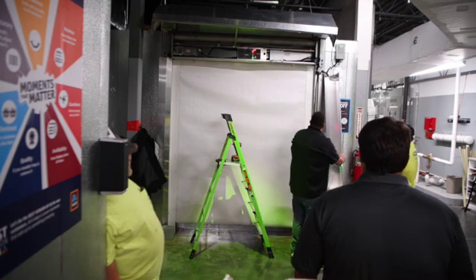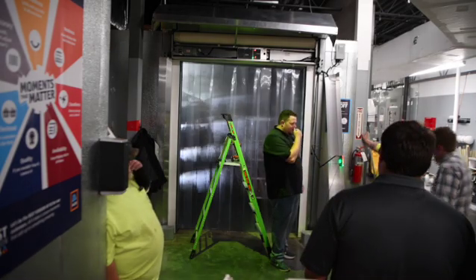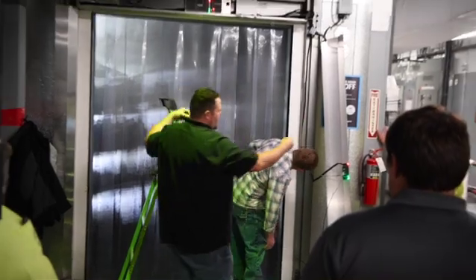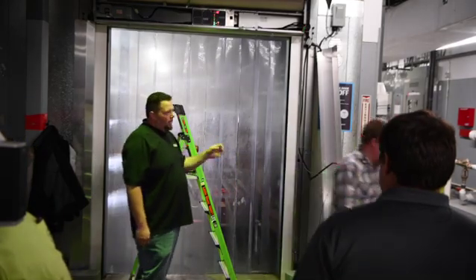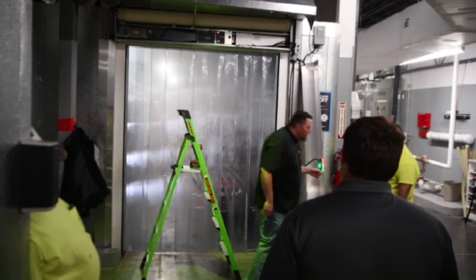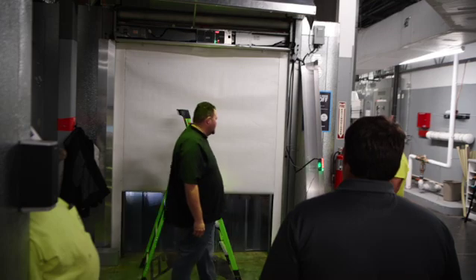You can see on the back side of this, that's the circuit board. That's where we're going to ask you if you're looking for moisture. On the install, which you guys have done plenty of now, these photo sensors, if you don't plug them in on that side, it's all going to come rolled up in this top bar and you have to feed it down. If you forget to plug up the side, the door's not going to work, but when you turn it on, that PS light's going to be lit up. And also, that's a 4-pin connector. The other issue with a 4-pin connector is you can turn it any way you want to and plug it in. So we've even went to where I think, this one's done before we made the change, but we put a yellow dot on the connector and kind of tell you what side's up. But if you get in there and look at it, you'll see there's basically a little cutout to catch the flip on.